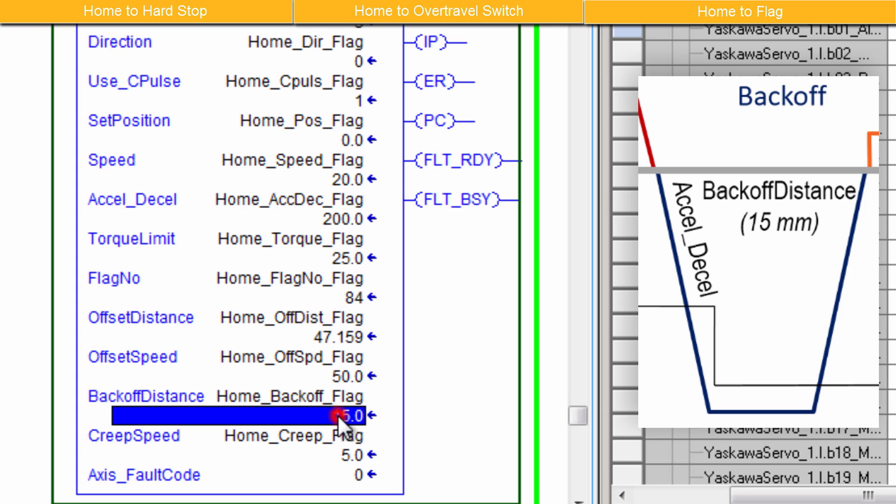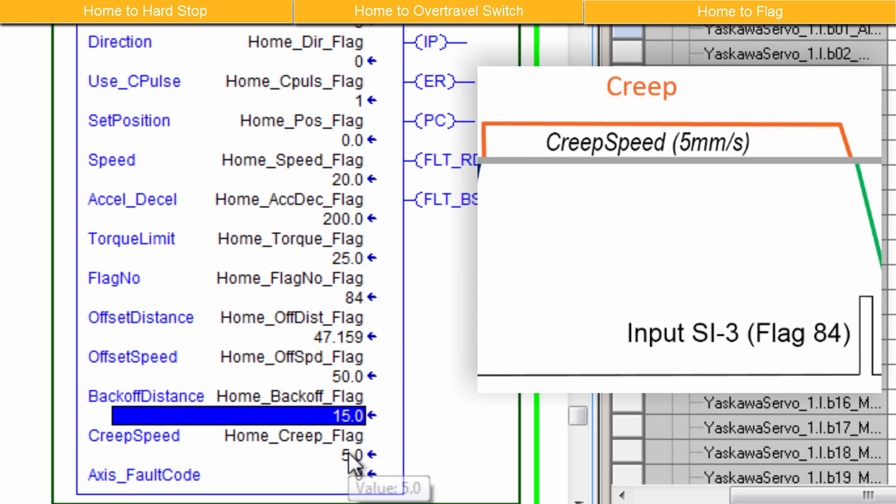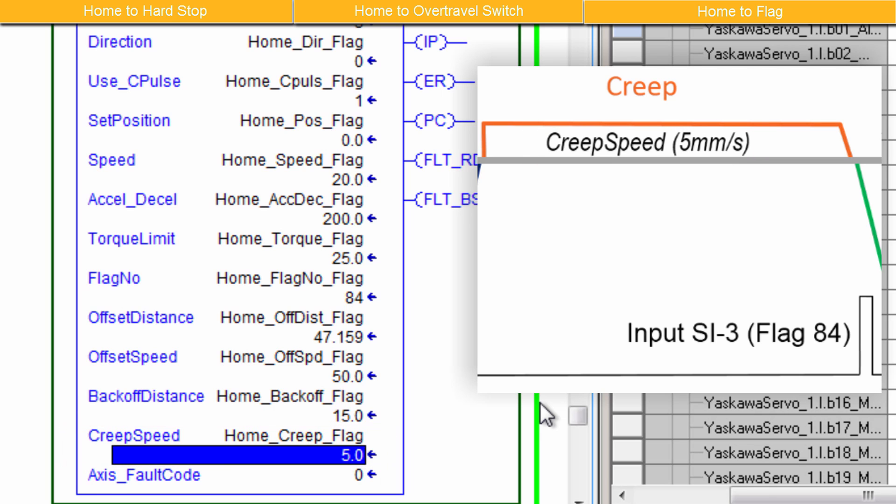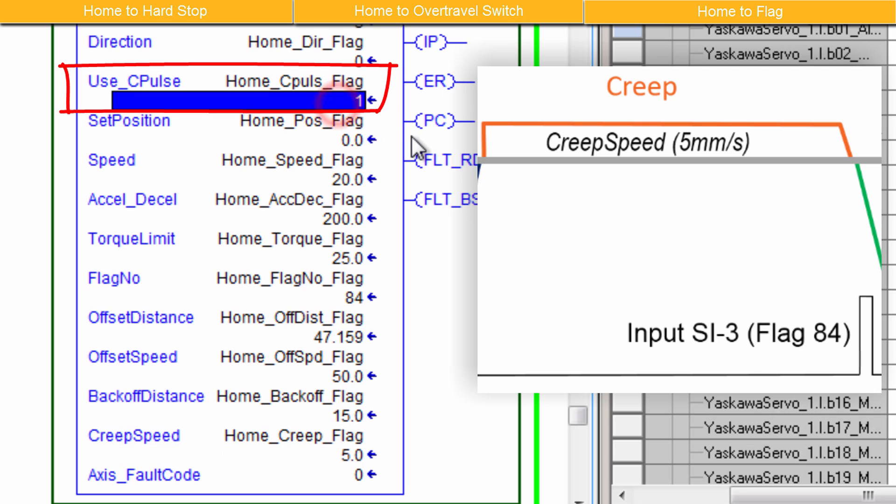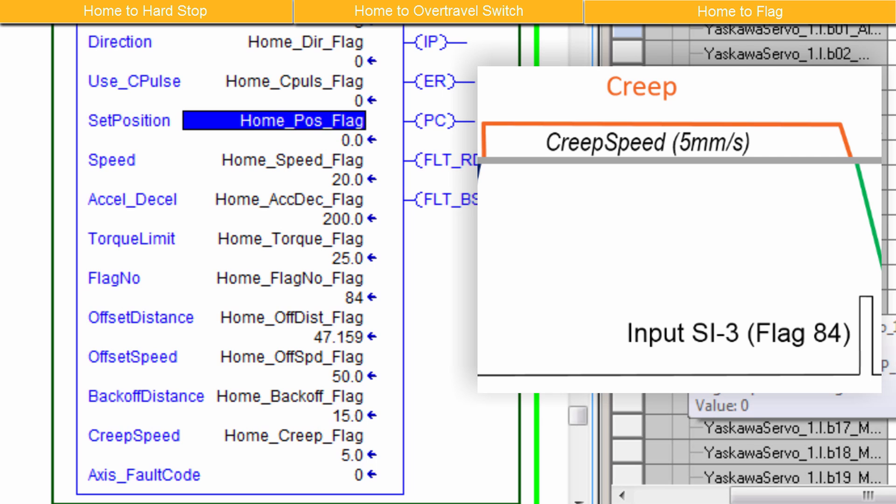We'll use a Back Off Distance to move away from the flag position. And I'll set that to 15. The Creep Speed will make the motor move slowly toward the flag position where it will stop. I'll set Creep Speed to 5 millimeters per second. And as before, Use C Pulse could be enabled to instead creep slowly away from the flag position, stopping accurately at the encoder's C Pulse. For now, I'll just leave it off.